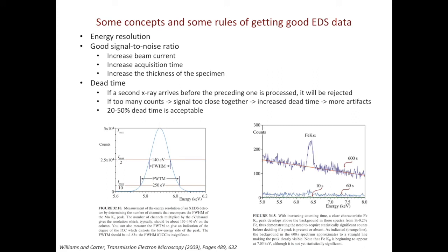The third strategy is to increase the thickness of the specimen. Remember in high res TEM, we want the specimen as thin as possible. But for EDS, we want the specimen more than one mean-free path in thickness. Thicker sample will increase the chance of inelastic scattering, thus more counts on the characteristic X-ray.